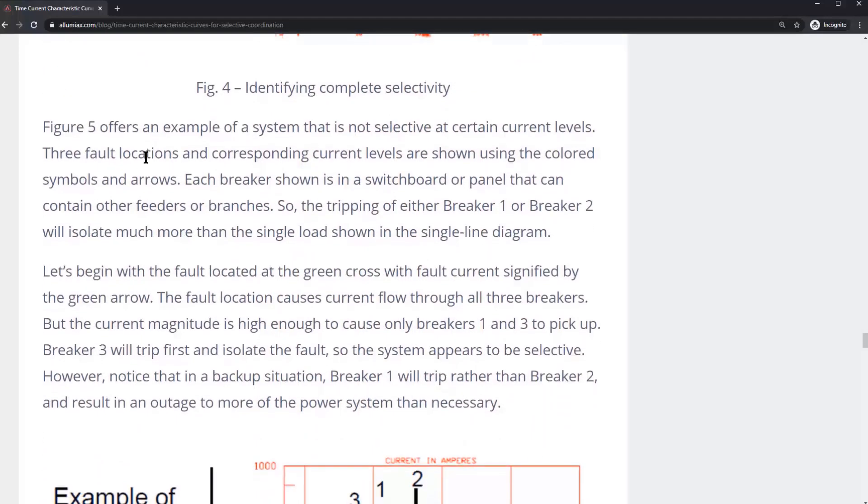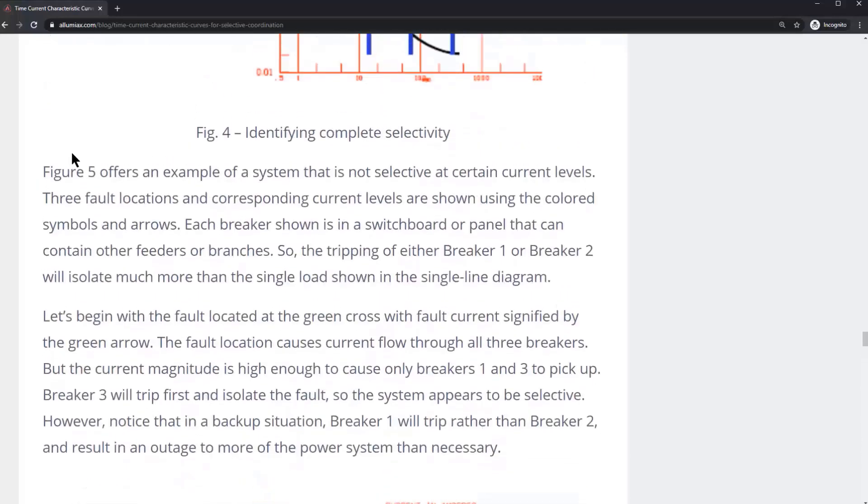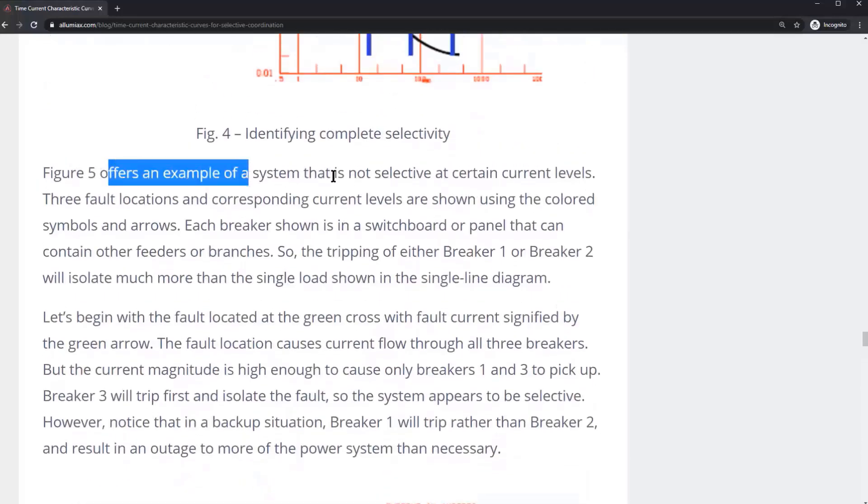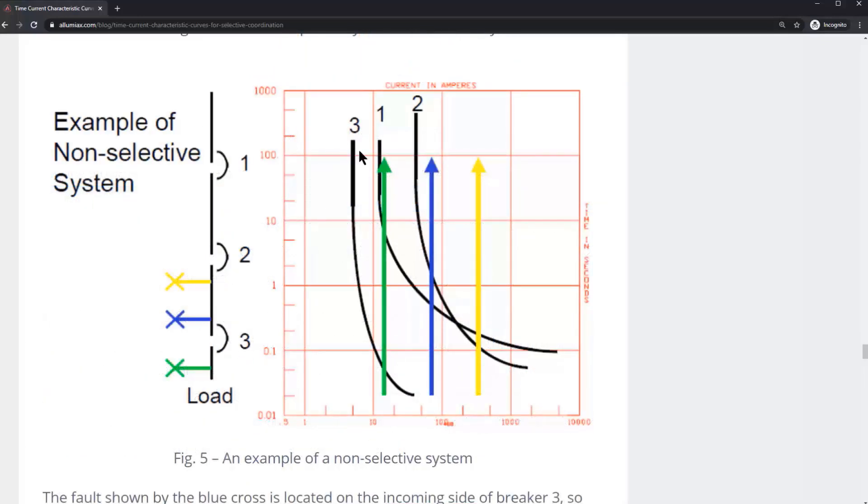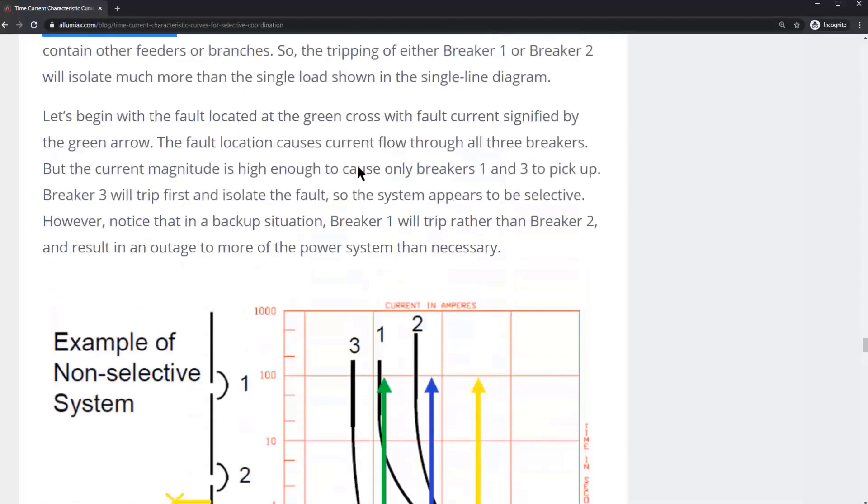Now Figure 5, which is this figure right here, offers an example of a system that is not selective at certain current levels. Breaker number three is furthest to the load and is the furthest to the left and the most bottom. Breaker number two is in the middle, and breaker number one should be furthest to the top.